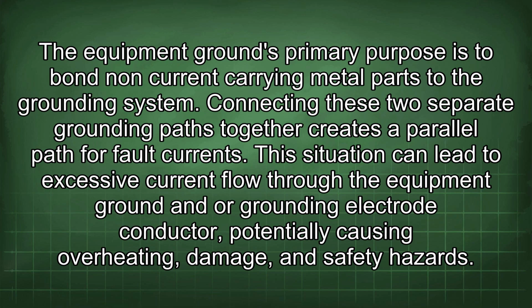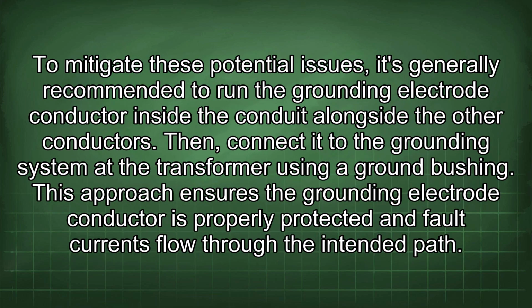This situation can lead to excessive current flow through the equipment ground and/or grounding electrode conductor, potentially causing overheating, damage, and safety hazards. To mitigate these potential issues, it's generally recommended to run the grounding electrode conductor inside the conduit alongside the other conductors, then connect it to the grounding system at the transformer using a ground bushing. This approach ensures the grounding electrode conductor is properly protected and fault currents flow through the intended path.